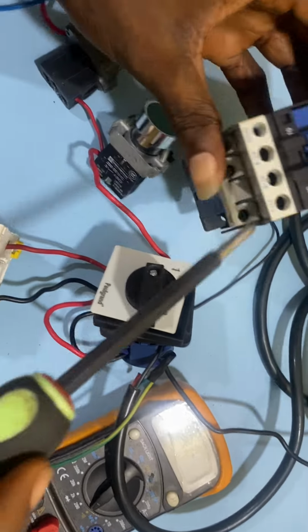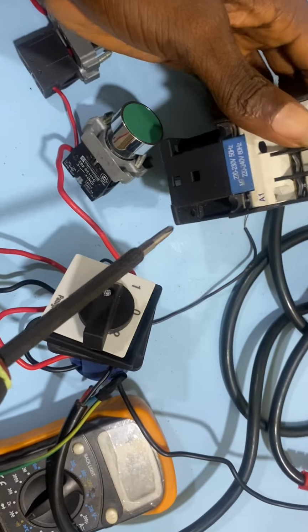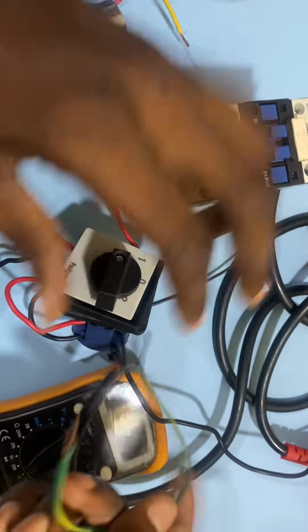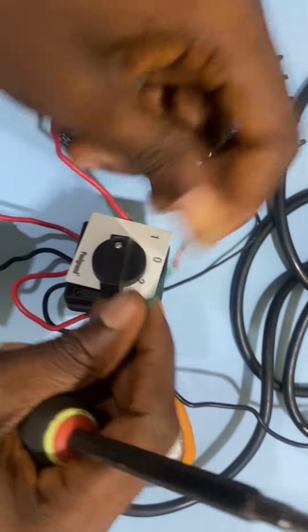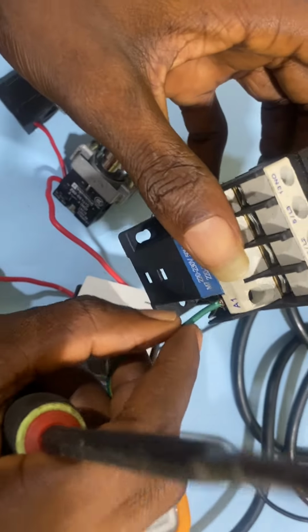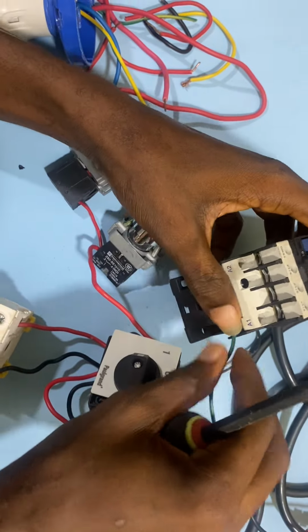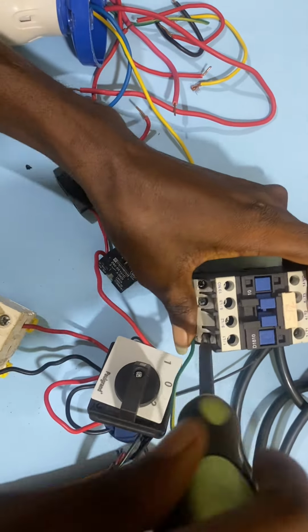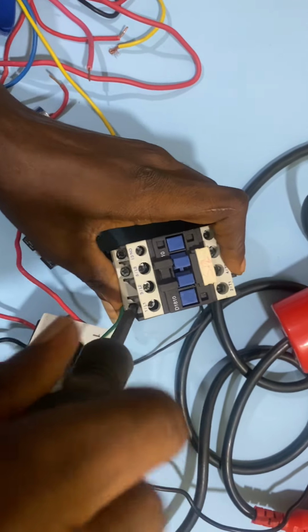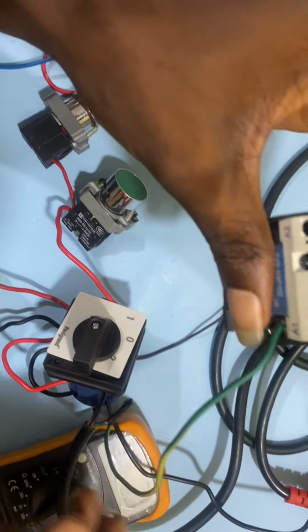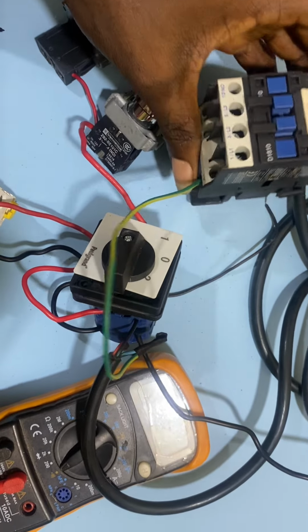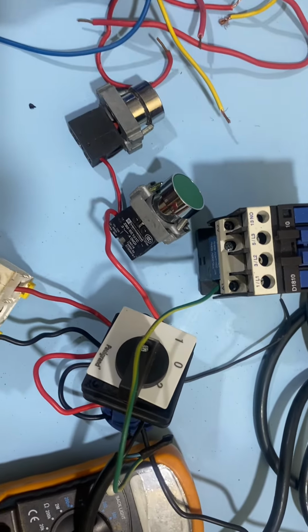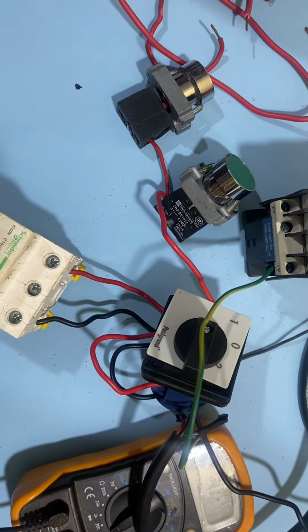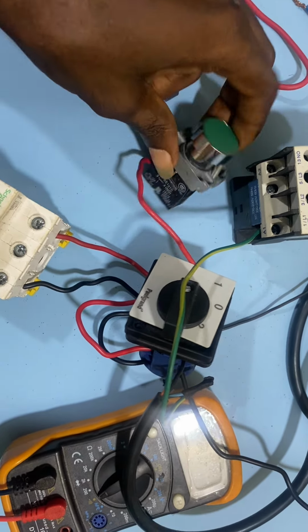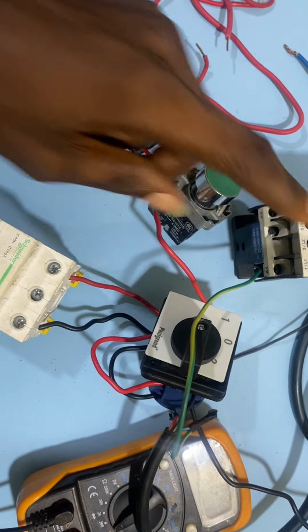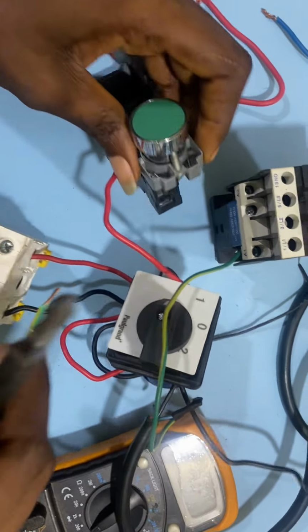So okay, let me first slot in the live from the flow switch. So this was my flow switch. This was the live output from the flow switch. So I'm connecting it at this point. Just follow the connection, you get it, slowly one after the other. So it's at this position now. So the next thing now is to also connect the one from my start button to the contactor. So I'm going to terminate at this point.